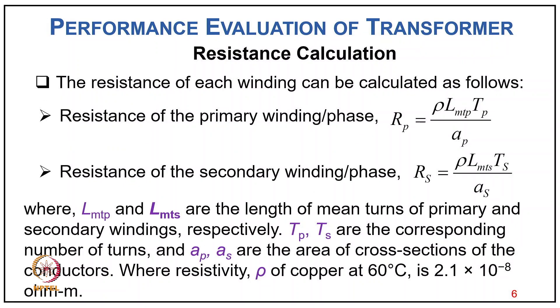The resistance of the primary winding per phase Rp equals rho × LMTp × Tp divided by Ap, and the resistance of the secondary winding per phase Rs equals rho × LMTs × Ts divided by As. Here LMTp and LMTs are the mean turn lengths of primary and secondary windings respectively, Tp and Ts are the corresponding number of turns, and Ap and As are the cross-section areas of the conductors. The resistivity rho of copper at 60°C is 2.1 × 10⁻⁸ ohm·meter.